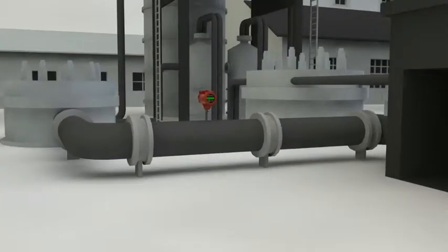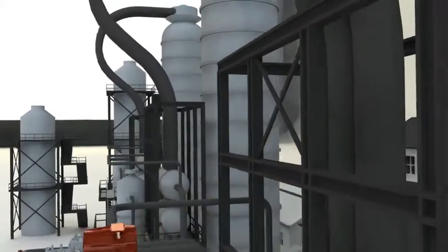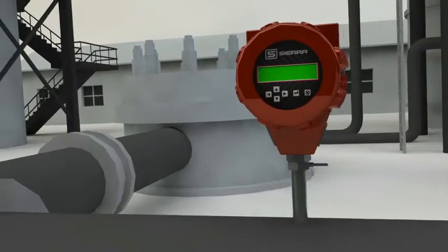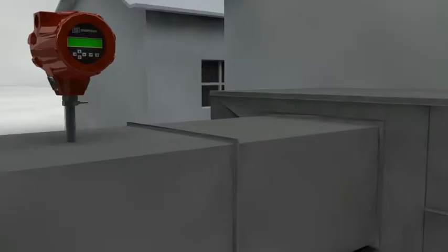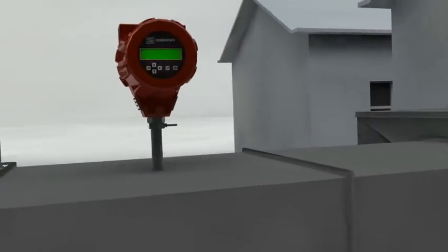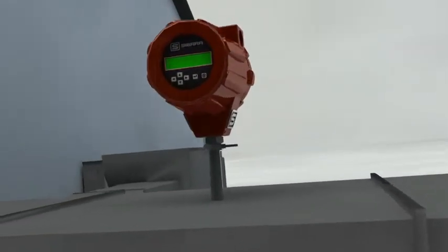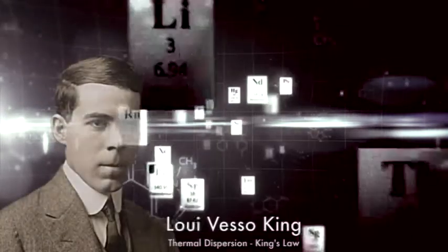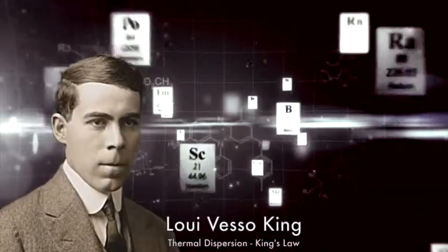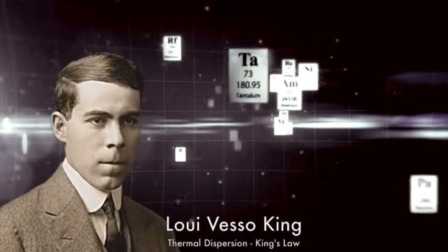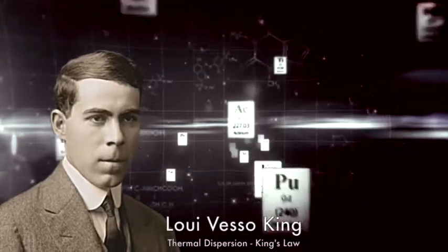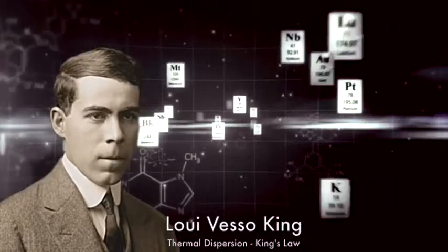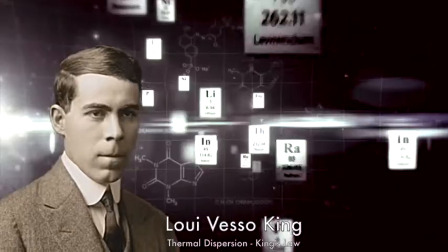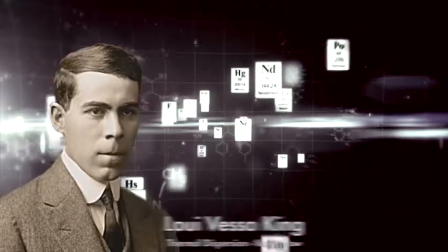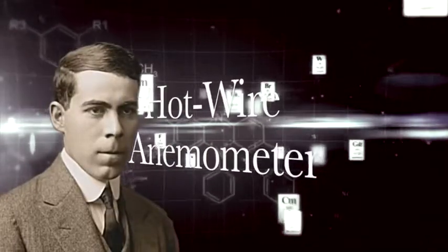Industrial thermal mass flow meters, also known as thermal dispersion or immersible thermal mass flow meters, comprise a family of instruments for precision measurement of total mass flow rate of a fluid, primarily gases, flowing through closed conduits such as pipes and ducts. The basic physics of thermodispersion mass flow meters is attributed to Louis Vessot King, who in 1914 published his famous King's Law, mathematically describing heat transfer in flows using a heated wire immersed in a fluid flow to measure the mass velocity at a point in the flow. King called his instrument a hot wire anemometer.